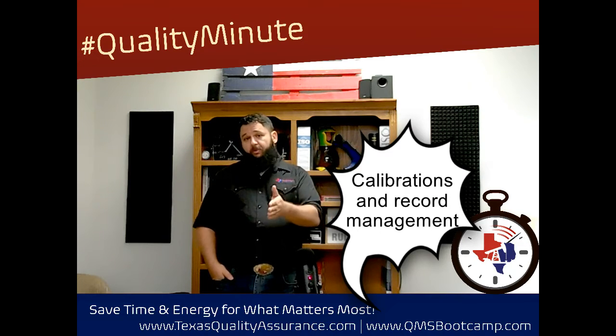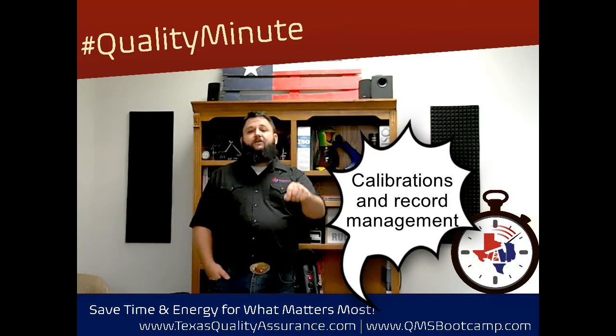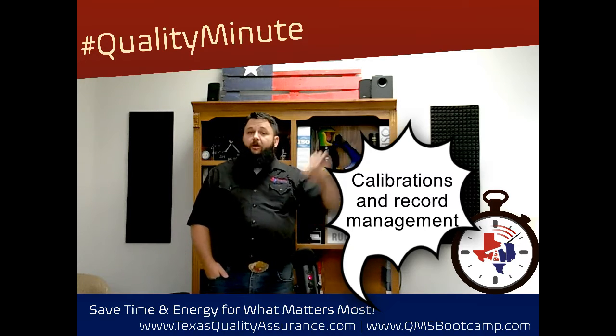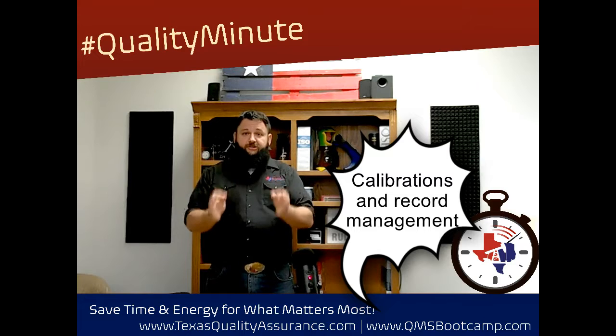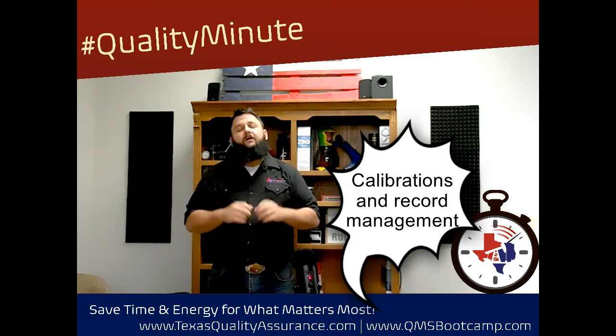Generally speaking, if the blocks are NIST traceable, which means that that block was checked with a piece of equipment that was recently certified to something else, then in any case you've got the whole train going all the way up to the National Institute of Standards and Technology, where these are certified blocks. They are exactly the dimension that we say they are.